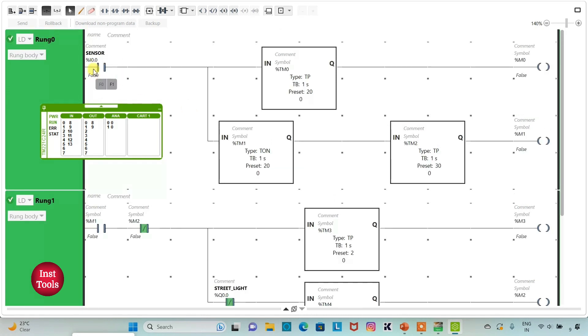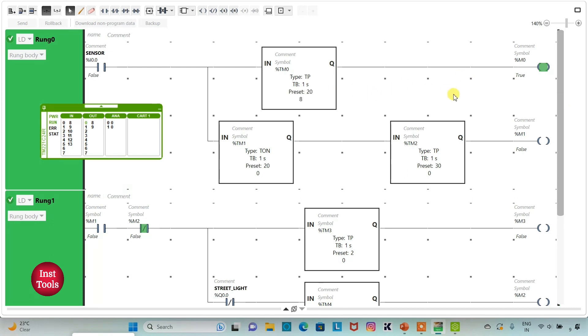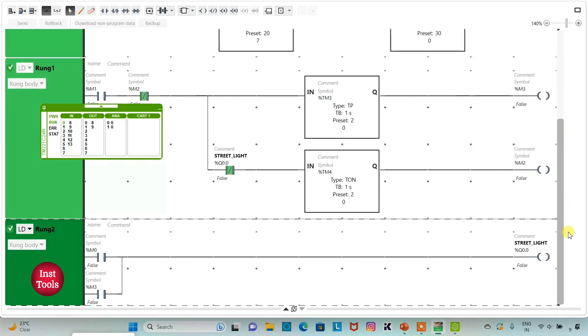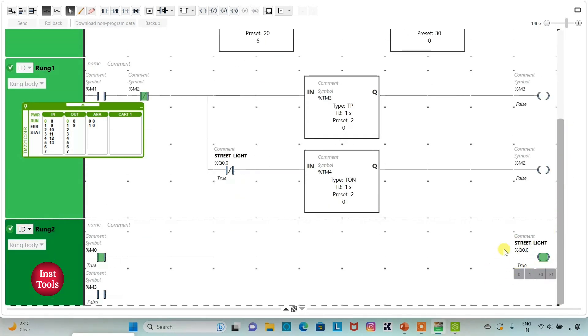So when the sensor detects any movement — that is when I0.0 gets true — M0 gets true. When M0 gets true, the street light will be true. M0 will be true for 20 seconds, which results in the street light also being true for 20 seconds. For M1 there will be a delay of 20 seconds.